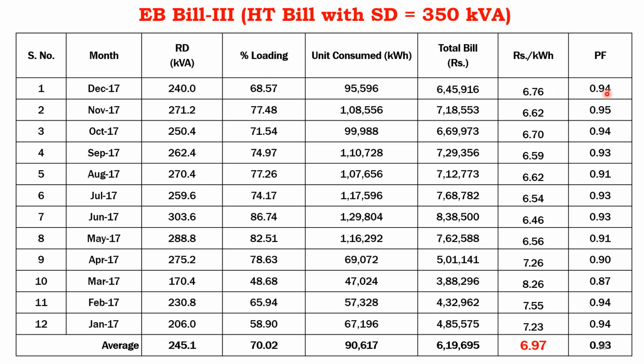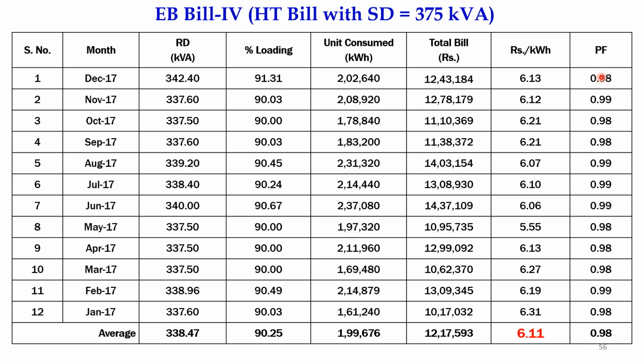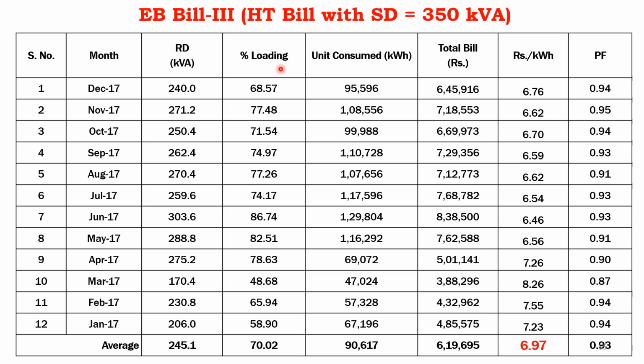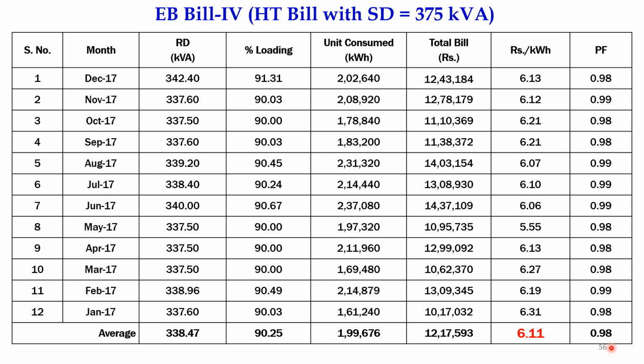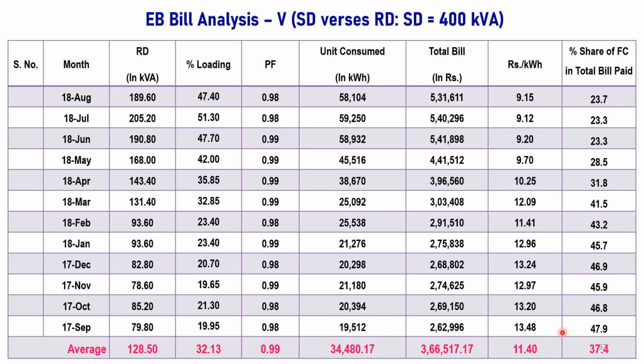Why? Because this company maintains a very good power factor and operates the load condition almost close to the sanctioned demand. Whereas here the sanctioned demand is not met. Of course, it is a 70% load condition, and similarly they are not maintaining the PF. That may be the reason for having a lesser value.